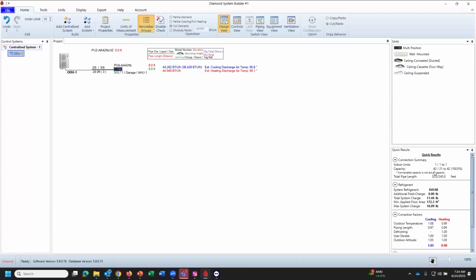We've got a one-to-one system. Capacity is 100%. Total piping length is 32 out of 245 possible feet. That 32 feet takes into account the bends that I put in there. System refrigerant is the 454B. Additional field charge is 0 pounds, 0 ounces.